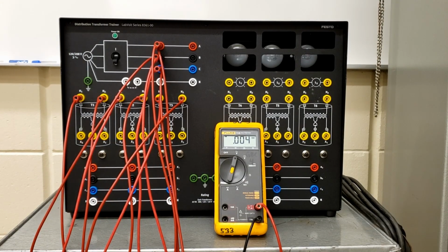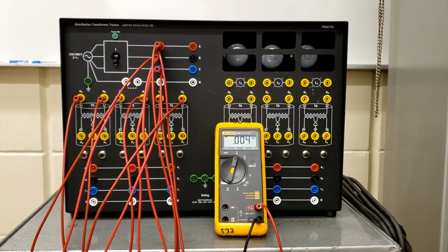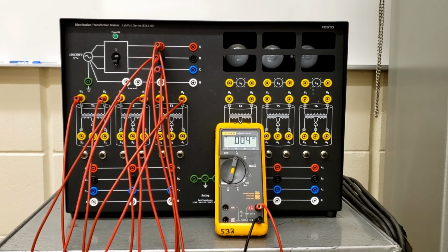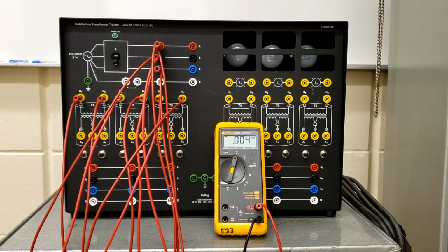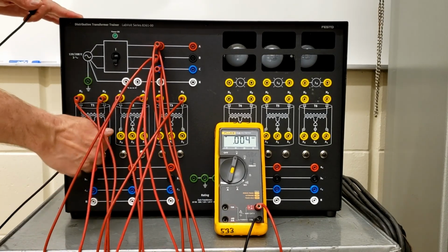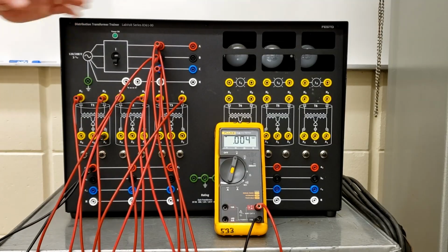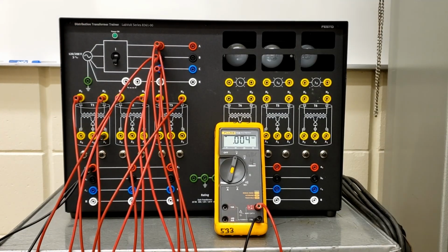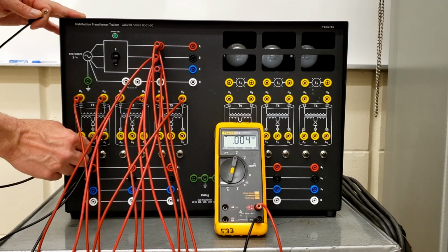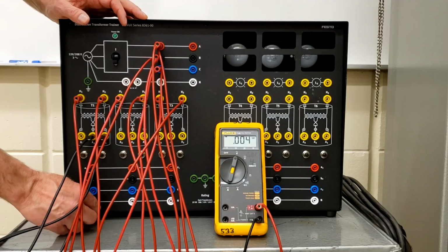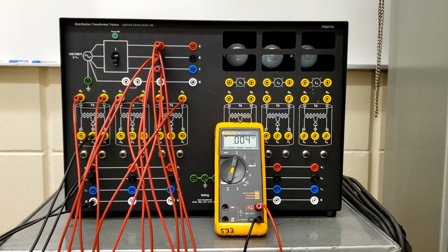Okay, now let's look at the secondary now. So this one's a little bit funky. We have X1 going to A. Okay, so X1 of the first transformer is feeding A. Okay, X2 is going to the neutral, and the neutral is going to be grounded. Okay, so we've got X2 going to the neutral, and we're going to bond that neutral to ground.